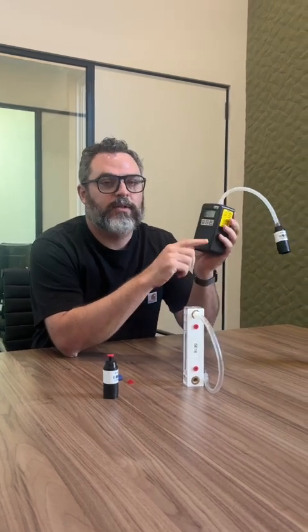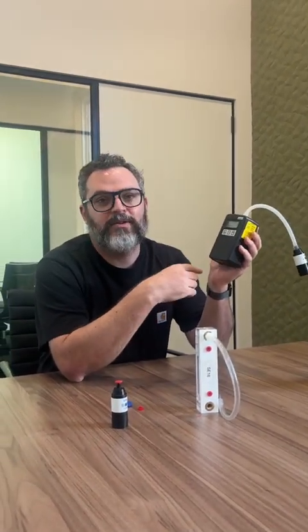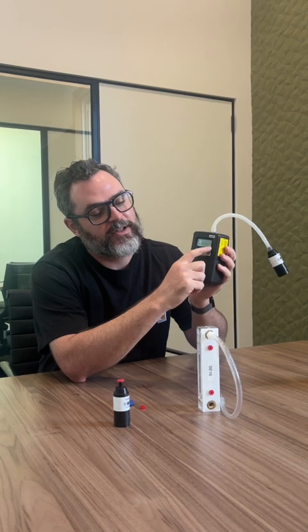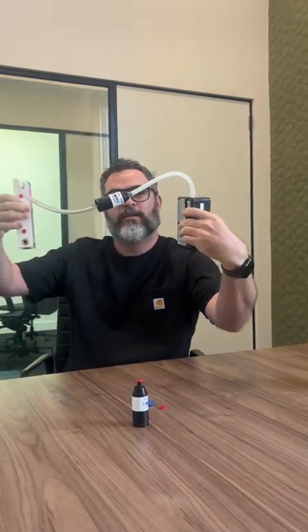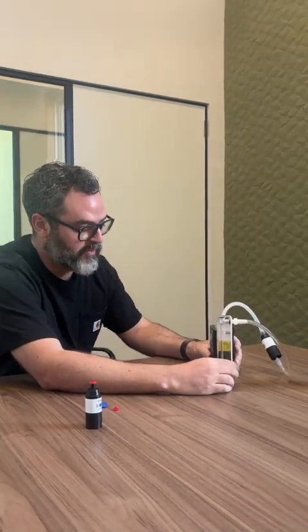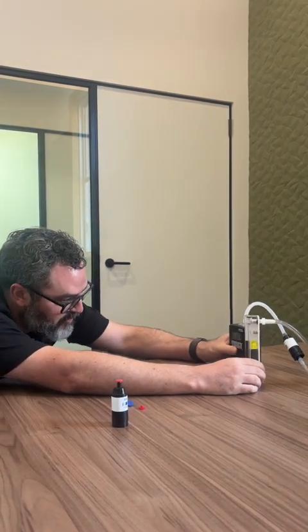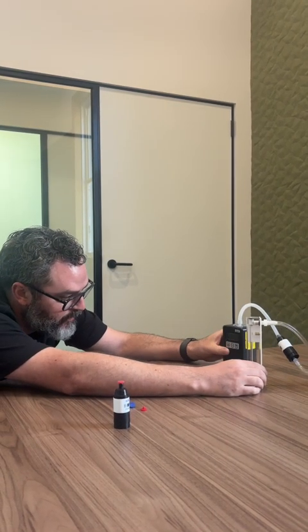So we need to get into our calibration mode. We all know how to do that. Middle, left, right, middle. Do that sometimes once, sometimes 500 times until you get into the screen. When you have the dashes in here, we're ready to go. And we plug where the little blue plastic stopper is, we remove that. And then we plug the rotameter in. So we have a nice train from pump to cal to rotameter. And we have the rotameter on a nice level surface.